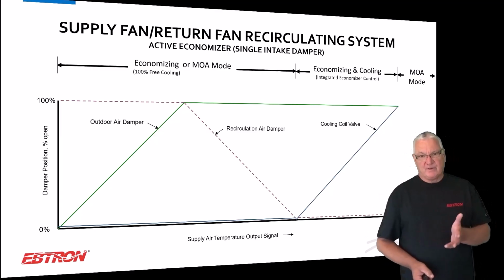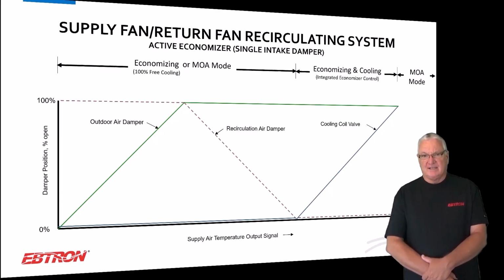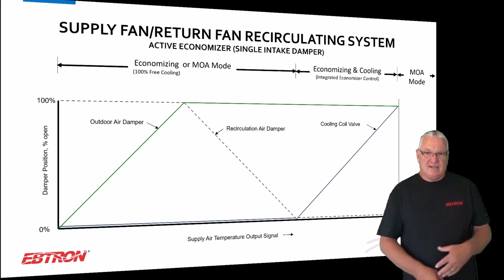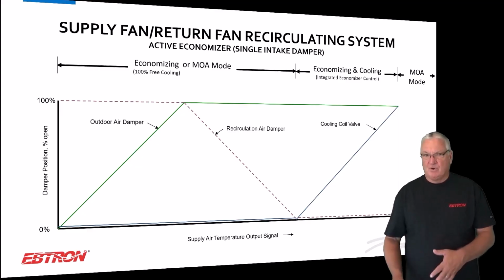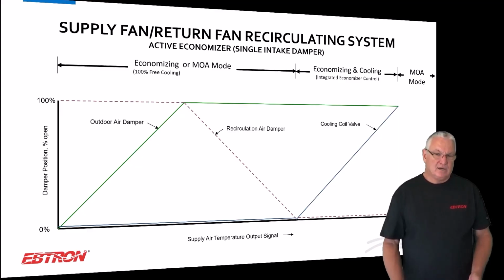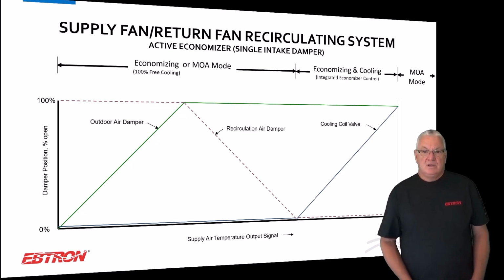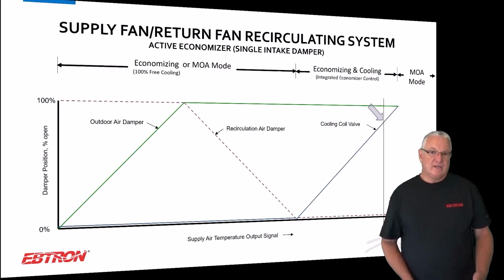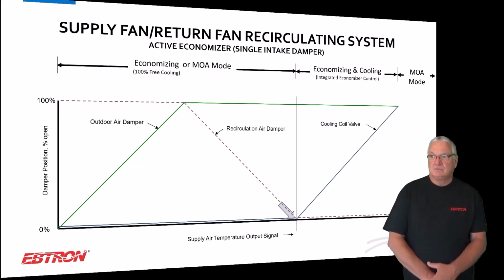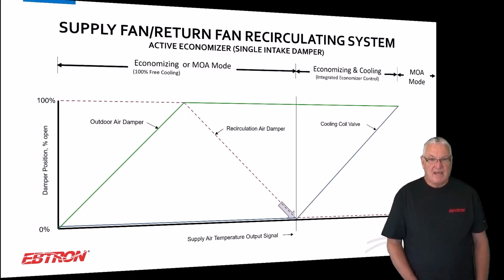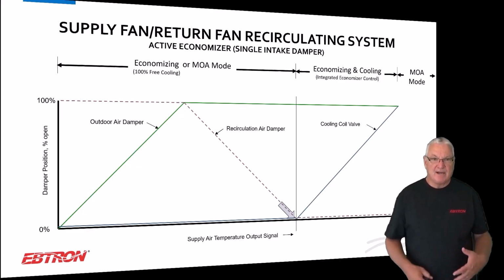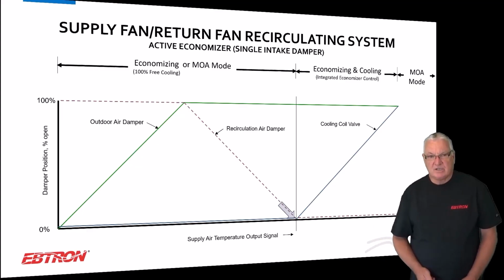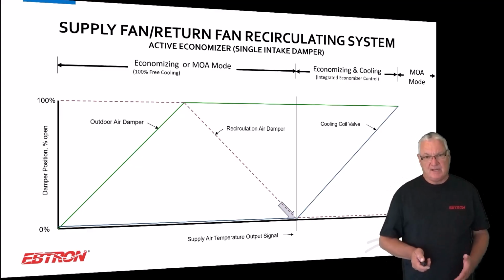Okay, and so I like to take people from right to left on this, where all the way on the right side, we're not economizing, we're in minimum outside air mode. And now we decided, for whatever our reasoning, whether it's dry bulb or enthalpy switchover, depending on where you are, that we're going to go into this integrated economizer mode, or economizing with cooling. So we're bringing in 100% outside air, and we're cooling that air. We finally get to the point where the outside air conditions are better than the supply air conditions that we want. So now as it's getting colder out, we go into a modulating economizer, and we start to back that down. And this is just a typical economizer strategy, okay?